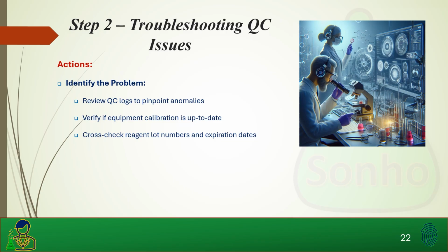Make sure that your calibration is up to date. What that means is your PM. So make sure that if the preventative maintenance is scheduled to be done soon, maybe it needs a maintenance, maybe more cleaning. Maybe the 3-month maintenance is almost up, and that needs to be updated to a 2-month maintenance. Maybe it's not happening regularly enough.